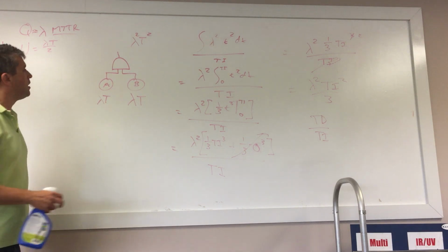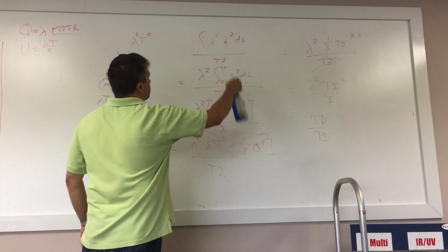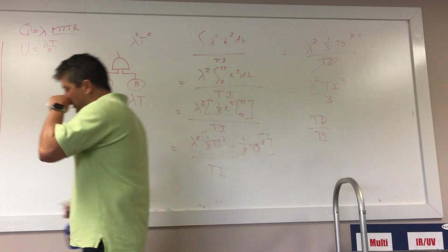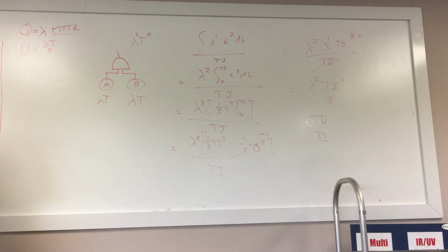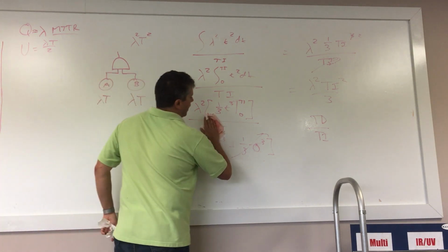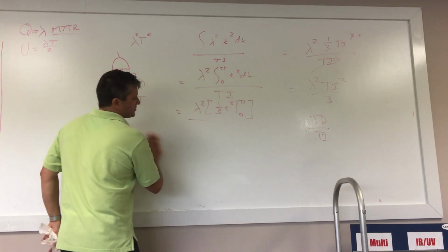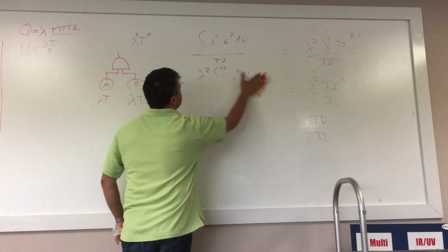and that is the assumption that's used in the Arbor software as opposed to the equation that you see here. The last term is new for systems that have a degree of fault tolerance against dangerous failures.